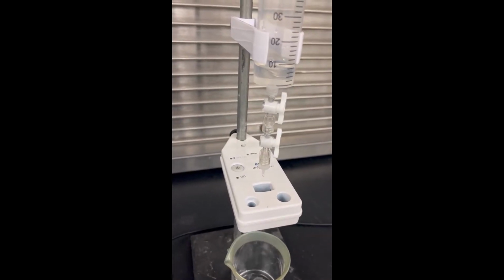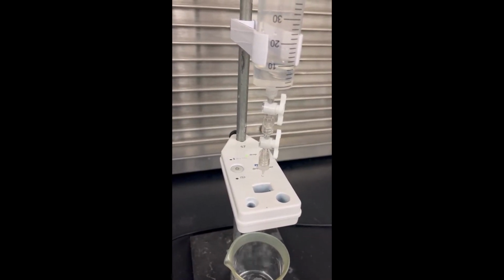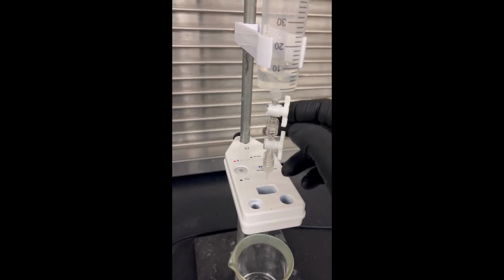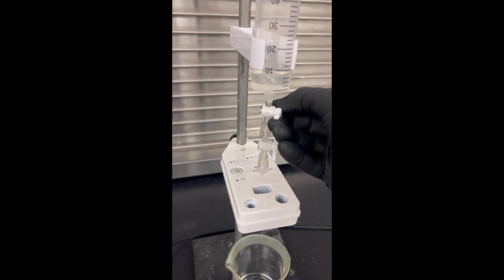Now make sure that the green light is flashing each time a drop passes through. Sometimes it only counts 1 out of every 2 drops or 1 out of every 3. If that is the case, you need to make sure you clean the inside of the drop counter.